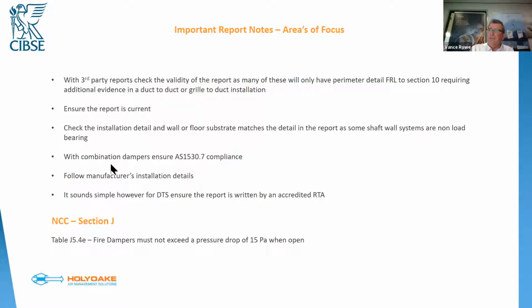Ensure combination dampers are certified to AS 1530.7. Please follow the manufacturer's installation details, right? And ensure that the DTS report is written by an accredited RTA. And finally, Section J. J5.4E requires fire dampers to not exceed a pressure drop of 15 pascals when open. Again, I think it's something that we all need to pay attention to out there in industry. So it's certainly something that we should be understanding.